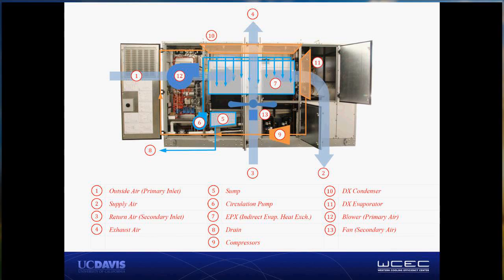The system can also be configured to operate using outside air on that secondary side of the heat exchanger when it's applied in a building that needs more positive pressure and doesn't have that secondary airflow available. For example, if it were installed in a grocery store, many grocery stores also include plenty of exhaust ventilation for their kitchens and their bakeries and their pizza ovens. The ventilation supply for the sales floor is typically used as the makeup air for all of those exhaust systems, and in that application there's generally not enough return air, quote, available to this unit without depressurizing the store. So in that application, you would use outside air instead.